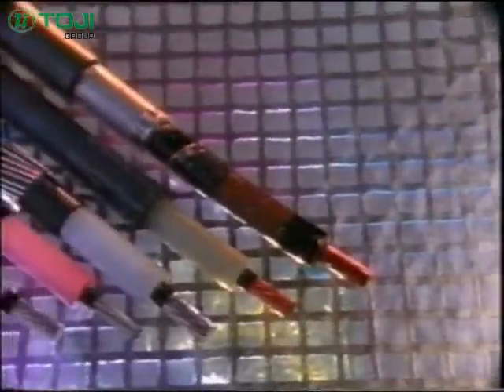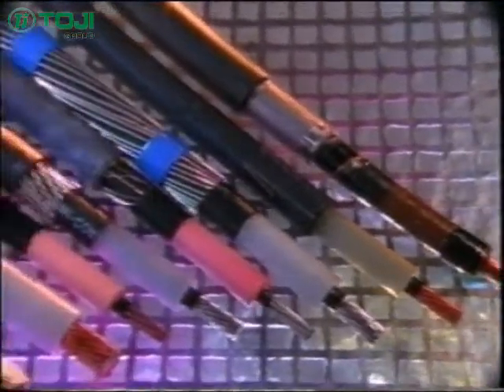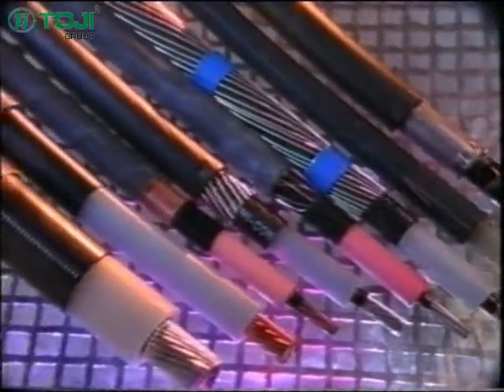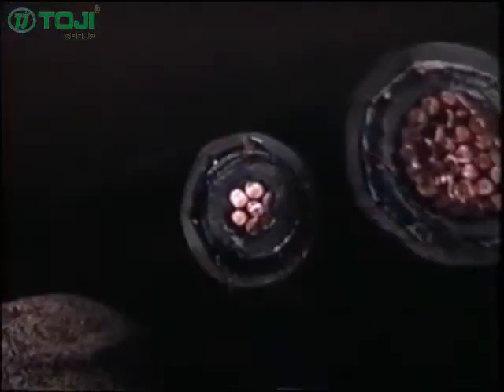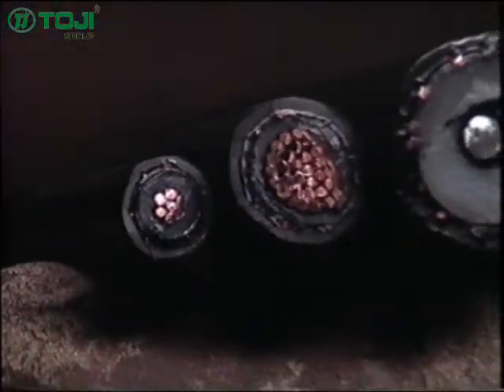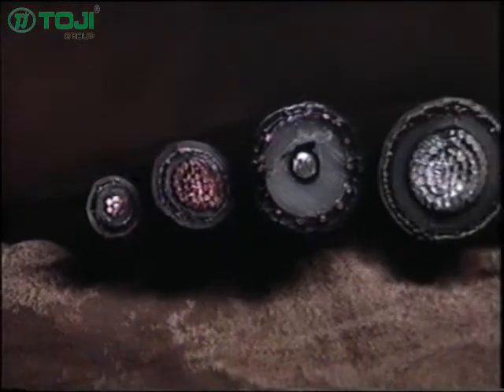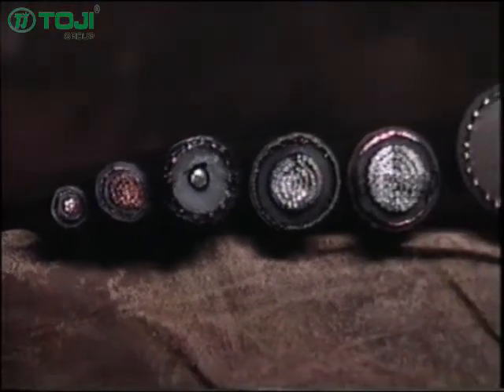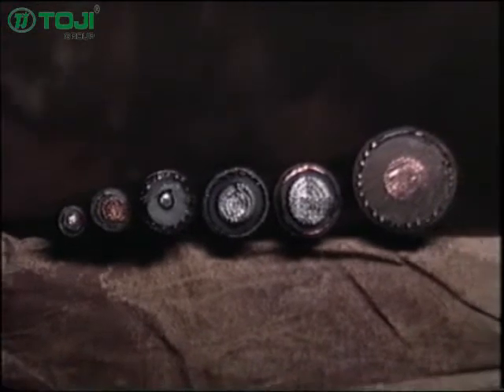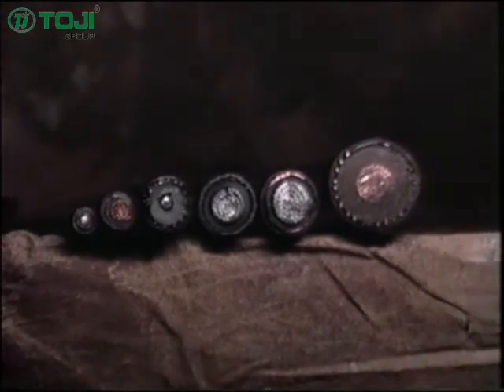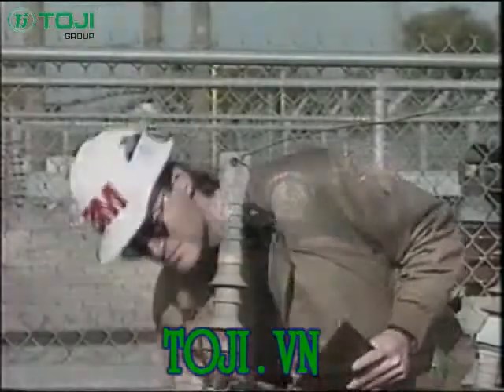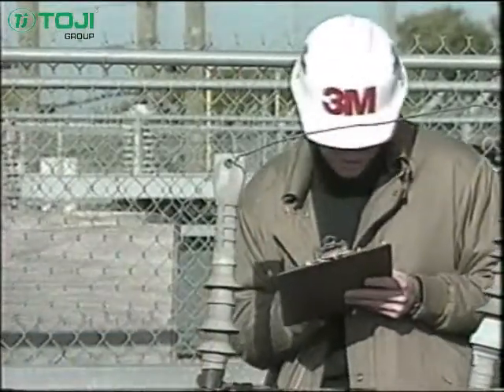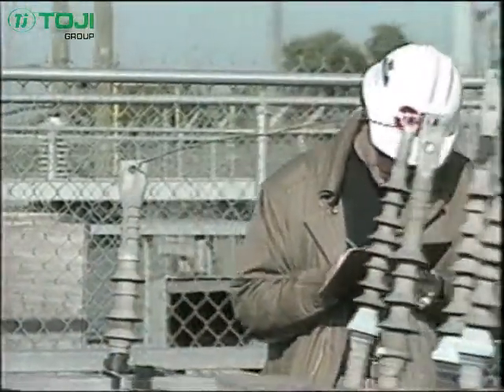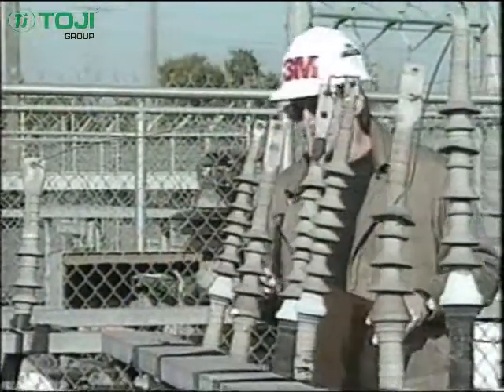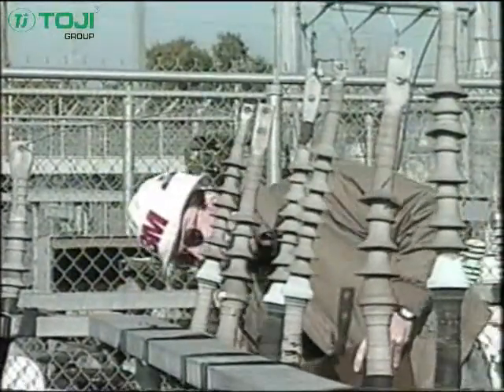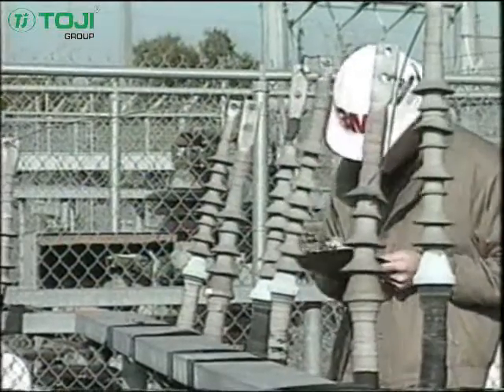3M has a Cold Shrink silicone termination solution for most every size and type of electrical cable manufactured and used today. The Cold Shrink QT2 termination line covers cable as small as number 8 5 kV, all the way through monster cable such as 1500 kcmil 46 kV on both solid dielectric and PILC cables. 3M's Cold Shrink terminations have a proven track record of reliable performance. Our products have maintained their superior performance and reliability since the early 1970s.